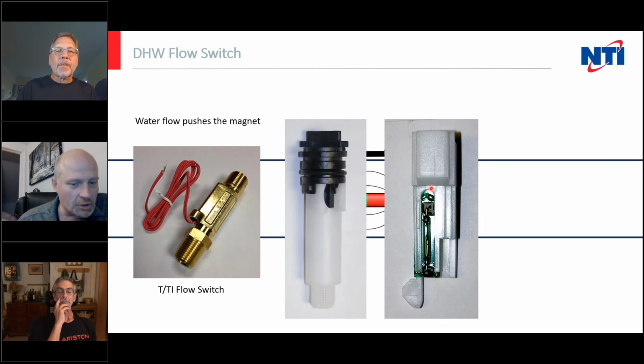If you stick a magnet next to it and your boiler activates for domestic, it means the reed switch works, and for some reason the magnet that's in here is jammed up or it's not getting pushed. And of course, if you stick a magnet next to this and nothing happens, there's a good chance that the reed switch is damaged or broken. Haven't seen too many of those unless they get wet, but it does seem to happen. The magnets themselves, not much happens to them, although they are susceptible to magnetic debris in your system. So if you've got magnetite, that kind of thing, that can be a problem for these because it'll bind them up and they stop working once they get dirty enough.